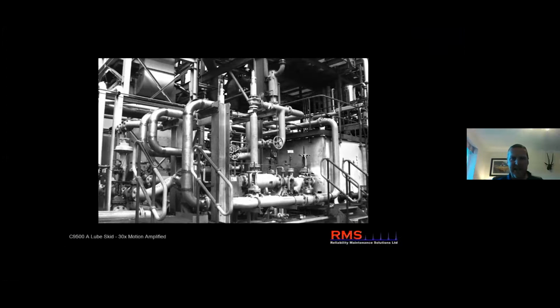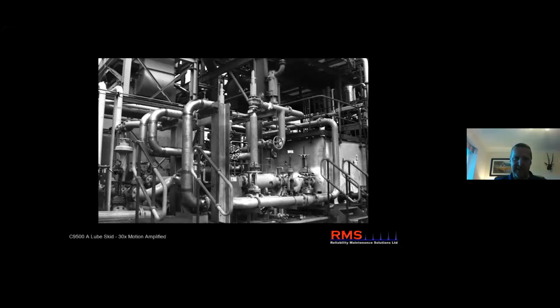So what you're going to see here is actually what happens when they switch over the pump, switching from an A to a B pump, and you can see this horrendous pipework motion. Right in the middle, there's a bit of small bore pipe. If you look at that, yeah, that is not good. I think that was over 200 millimeters per second on that. And sure enough, we actually broke it during this test. You can see that it's failed.